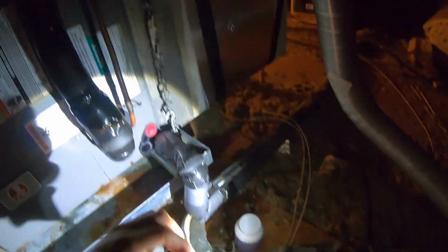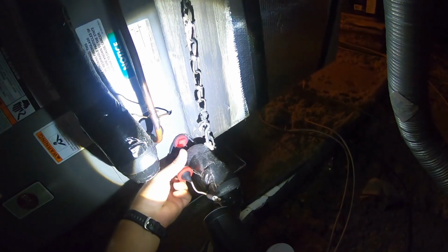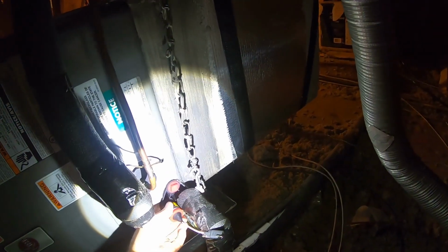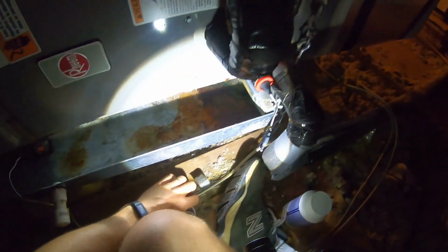Now, this switch that I showed you is not the most common one in the world, it's an AquaGuard. You'll more likely have a float switch. They're a lot less annoying than these things are. These things, even if they look at water, they trip. But they work very well. So I'm just screwing this back in. And then we plug in the electrical connector, and this unit should be good. Just like that. And if this thing got tripped, a red light will show up down here, so we'll just make sure that that doesn't come on. We'll sit here for a minute.